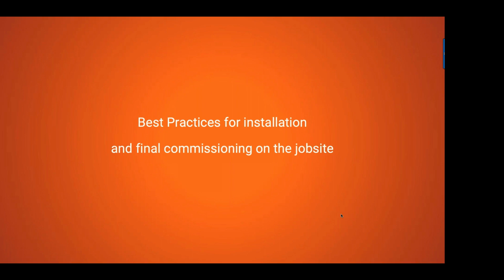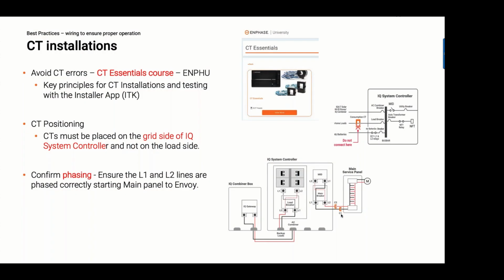We just talked about things that you should do before you go on site. Now let's talk about things that you should really think about while you're on site. And these, again, are some of the key things that we think are high value targets in terms of focus. All right. So the first one is related to CT installation. CTs, of course, are current transformers that are related to the metering system.